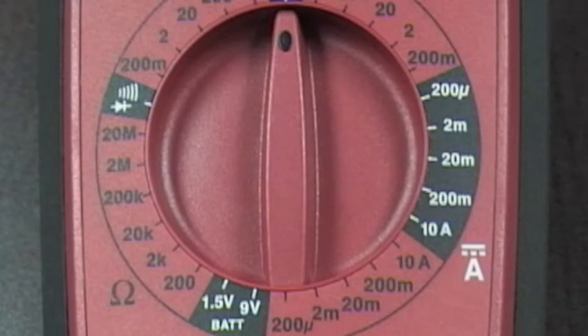When making your selection, choose a range that is just above the value you expect to measure in order to get the most accurate reading. If you are unsure of the possible value, select the highest setting and work down. This is always a good idea if you are dealing with high voltages.